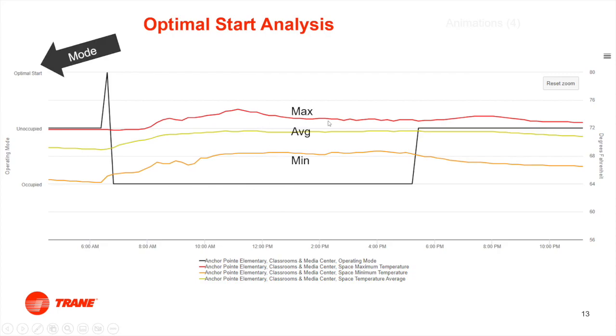So what we have here is we have our max temperature of the space, we have our minimum temperature of the space, and then we have our average. Well, if you're looking at this data, there's a lot to take away from here. Number one, we have a 26-minute optimal start, which means, based on the outside air temperature, it needed to start 26 minutes early to get happy by whatever its occupied start time is. But look at this - it took an additional 3 hours for that space to get comfortable.